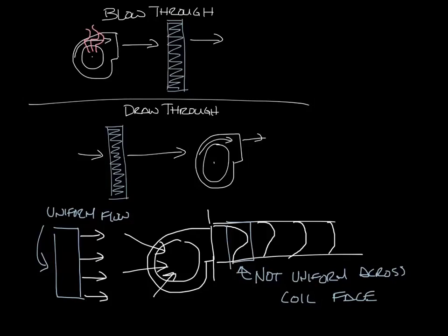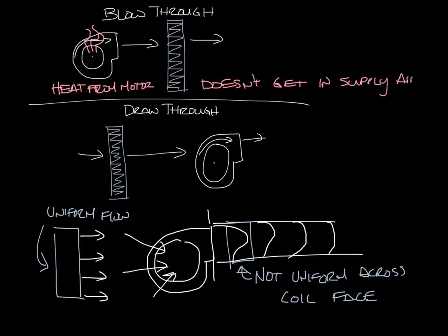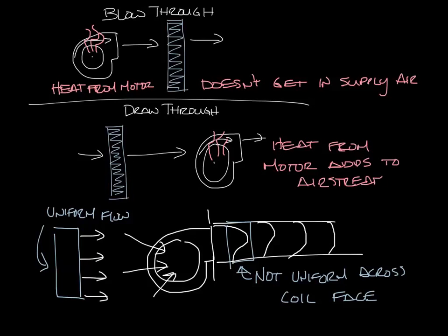One benefit to blow-through configuration is that the heat from the motor is not added to the airstream after the coil. Whereas in a draw-through system, the heat coming off the motor will be added to that air that's being supplied to the space. So you'd want to account for this in your system design.